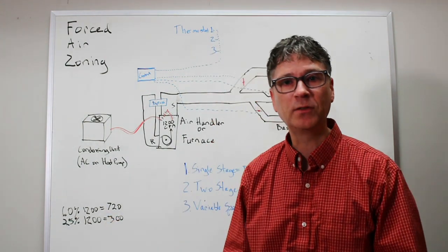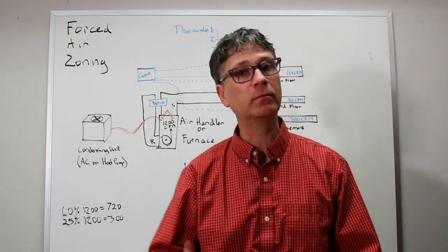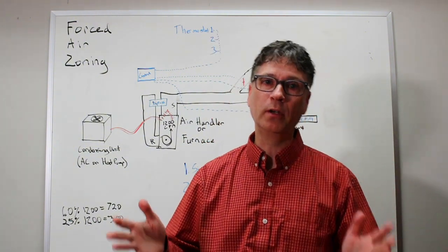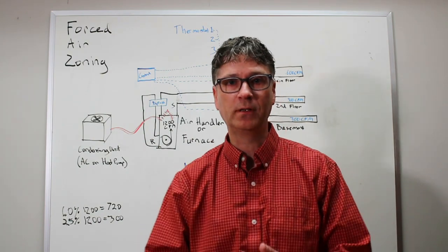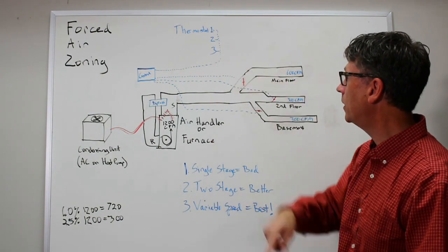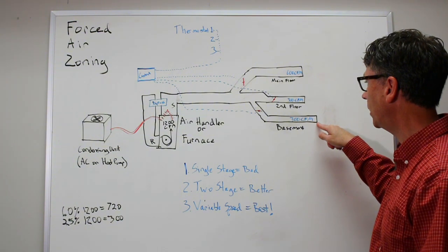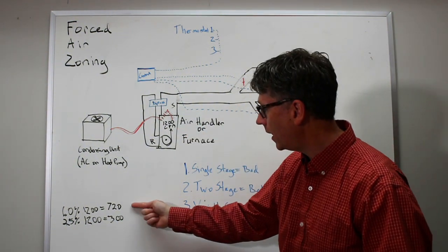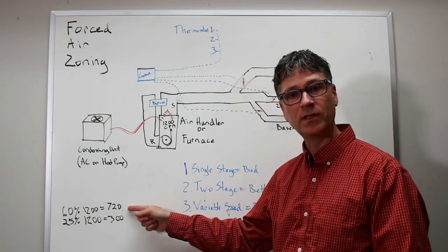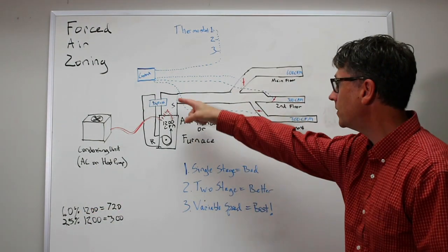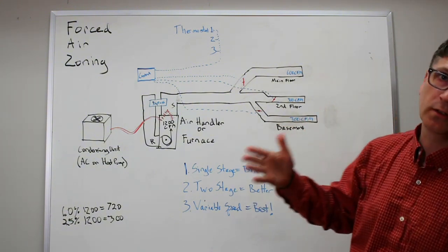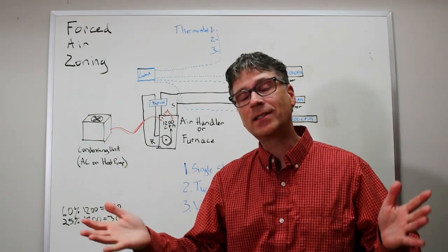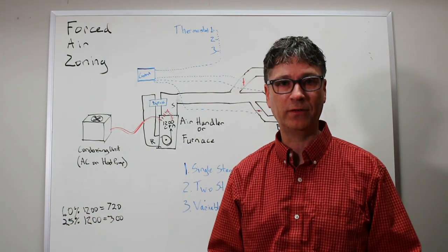Well, a half step is to install what's known as a 2-stage system, usually coupled with a variable speed air handler. The system can partially balance the output with the load. Let's look at the example again. Let's say this time zone 3 calls. Zone 3 is another 300 CFM zone. The unit comes on, but because it's 2-stage, it comes on at 60% or 720 CFM. So 720 CFM starts the system, 420, the difference, doesn't know where to go. It's a lot better, but it has the same problem as before, a little less severe.